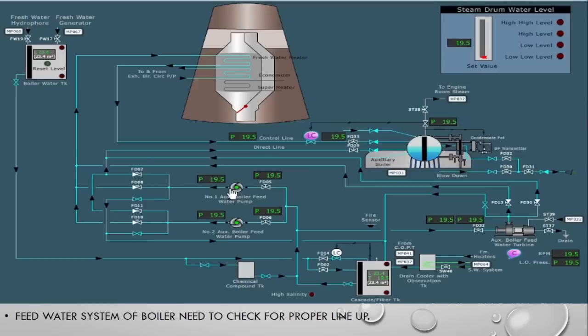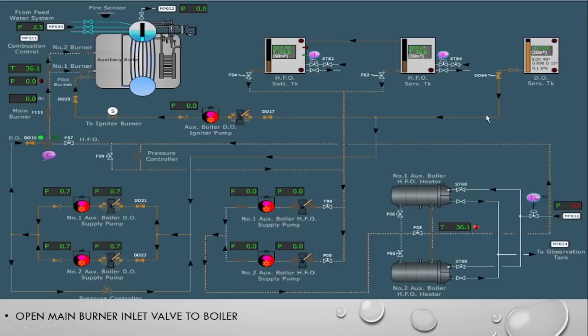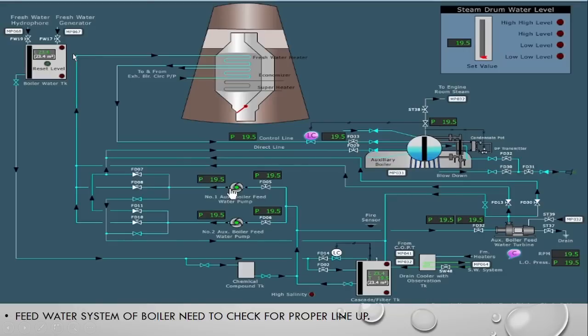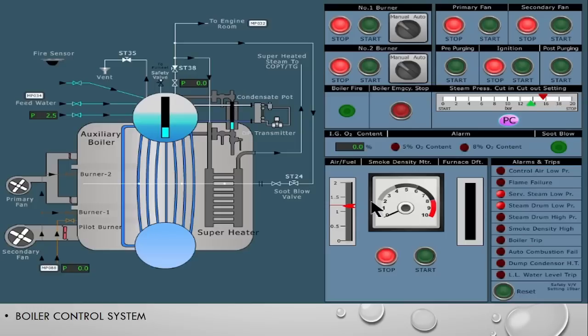So let's start the boiler fire. Till now we have lined up the igniter pump, lined up the boiler DO pump, and made sure that all valves in the DO line are open. After that we have made sure that the boiler feed pump is running and developing pressure, the water is coming in auto mode to the steam drum, and the boiler circulation pump is started if we are running the engine.